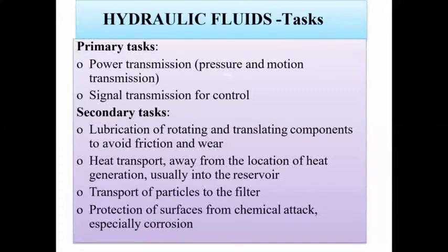The second one is signal transmission for control. Then the secondary tasks are the lubrication of rotating and translating components to avoid friction and wear, then heat transport away from the location of heat generation, usually into the reservoir, then transport of particles to the filter. These are the tasks done by the hydraulic fluid.